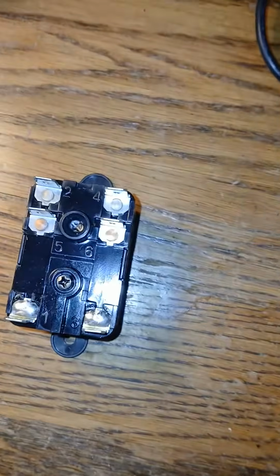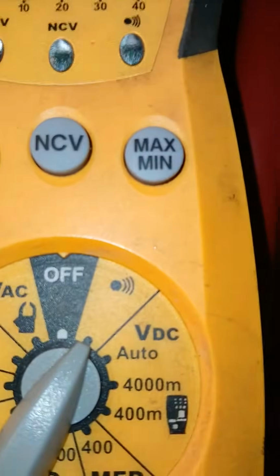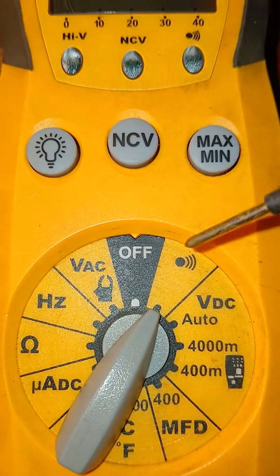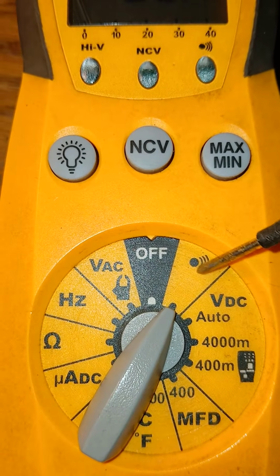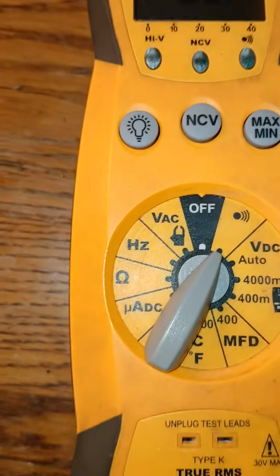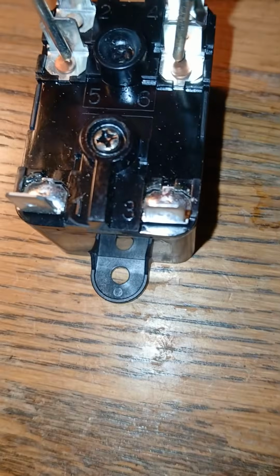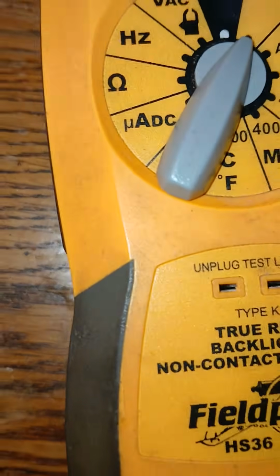Okay, so now we go to the high voltage. We flip this up to continuity. Continuity means it's a circuit. It's this little symbol here. On some meters it may be different, but it should give you a noise. You can see this for the noise here. The arrow is pointing in this direction. We cross over this coil. We're crossing over 5 and 6. You can see the meter is even giving us a green light. So 5 and 6 is good. That means that should be closed.